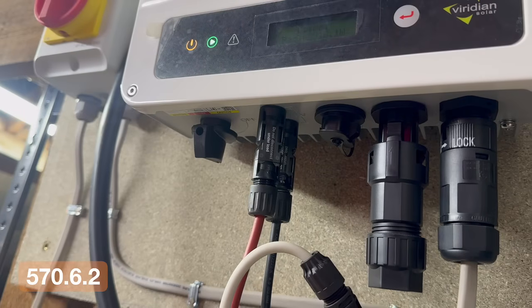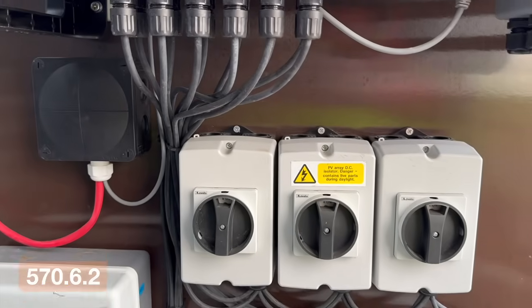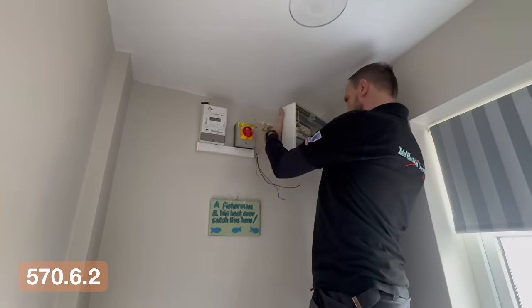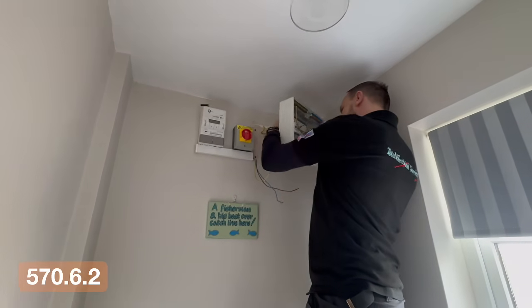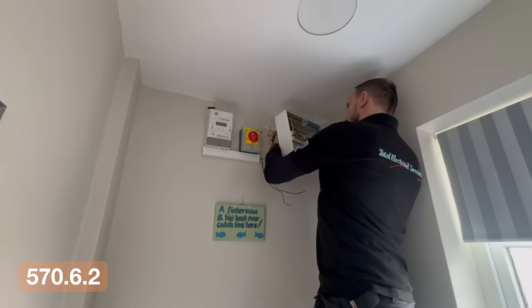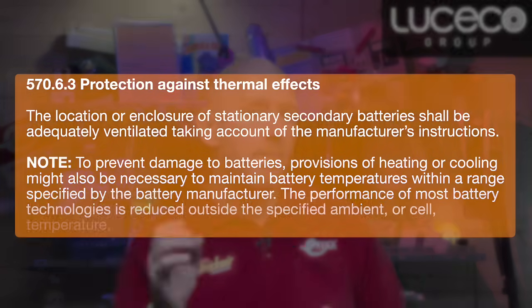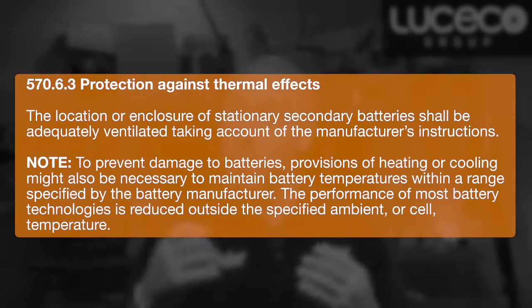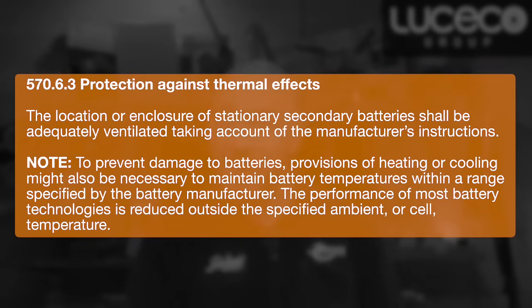Regulation 570.6.2 requires a Type B RCD unless certain conditions are met. This is because of DC components from the power conversion equipment. So if you install the wrong type of RCD here, it may not operate correctly under fault conditions. Thermal effects also come into play. Regulation 570.6.3 requires batteries to be adequately ventilated because depending on the type, they can generate heat or even release flammable gases. Which leads us into location.